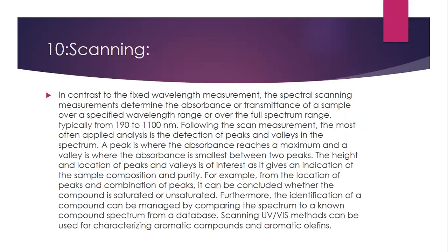The last application is scanning. In contrast to fixed wavelength measurement, spectral scanning determines the absorbance or transmittance of a sample over a specified wavelength range, or over the full spectrum range, typically from 190 to 1100 nanometers. The most commonly applied analysis following a scan measurement is the detection of peaks and valleys in the spectrum. A peak is where absorbance reaches a maximum and a valley is where absorbance is smallest between two peaks. The height and location of peaks and valleys indicates sample composition and purity. From the location and combination of peaks it can be concluded whether a compound is saturated or unsaturated, and compounds can be identified by comparing the spectrum to a database of known compound spectra. UV visible methods can also be used for characterization of aromatic compounds.